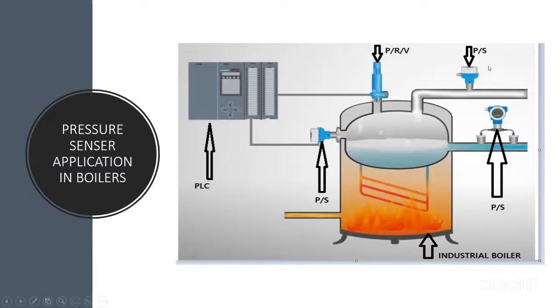We also have the third sensor shown here, which can check the pressure of steam sent to the destination machine. Assuming the boiler is at about 8 bar, and the destination machine requirement could be, we say, 5 bar or even 4 bar. For example, if it is 4 or 5 bar, then with the help of this pressure sensor, we can now tell the system to open.